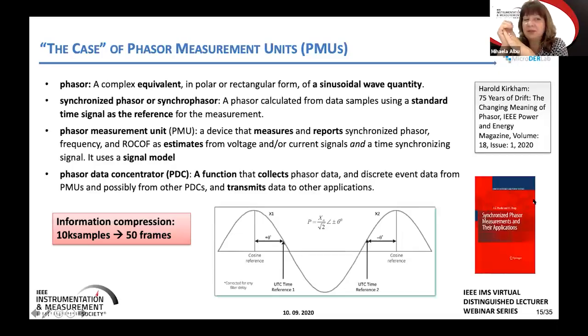But the most important thing is that PMUs use a signal model, and that signal model is embedded into the definition of the PMU, embedded into the standard. This is not like other measurement equipment, which is defined up to a very general level, with quality only afterward associated with the measurement equipment. It's a kind of unique decision to have the PMU embedding so much of the signal model.